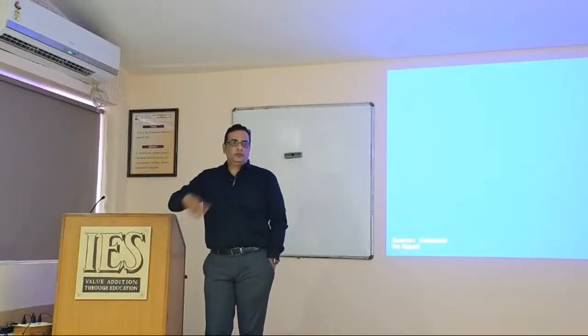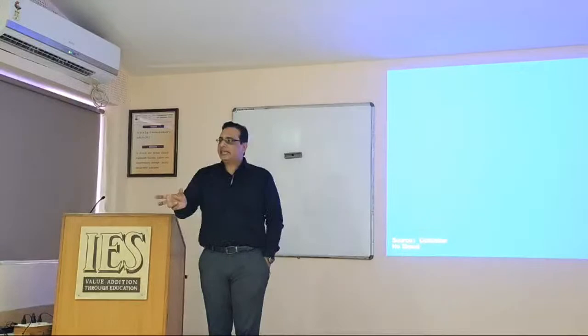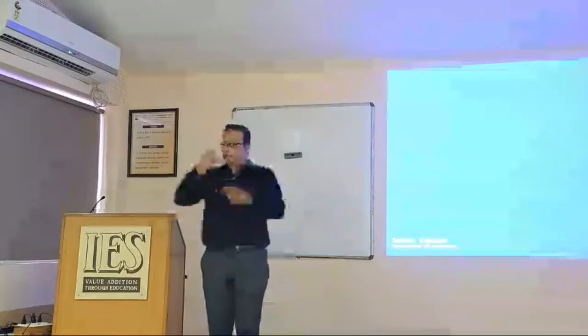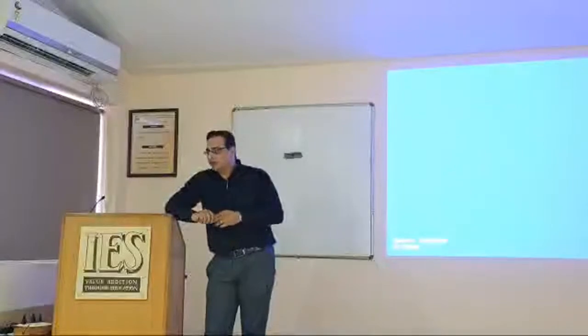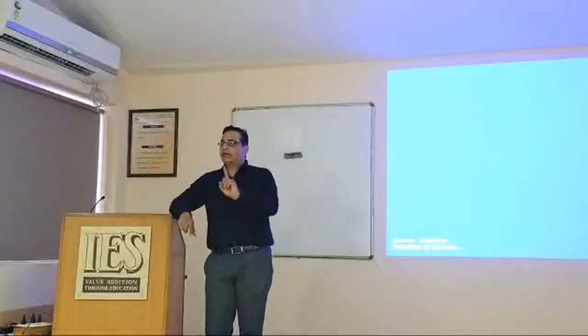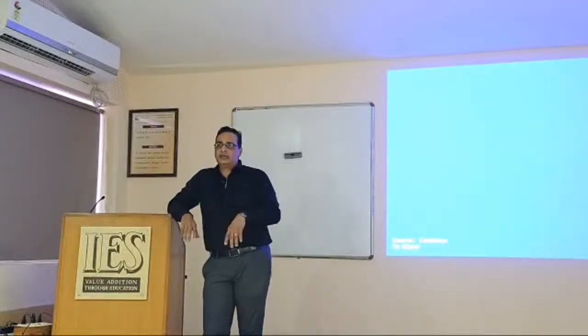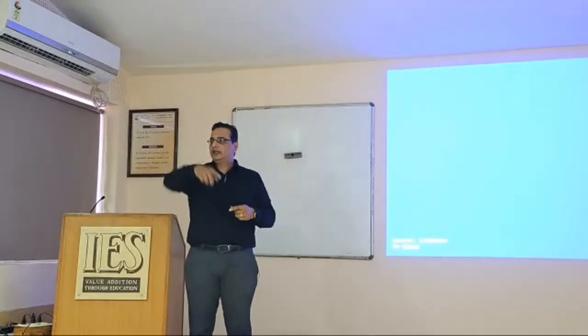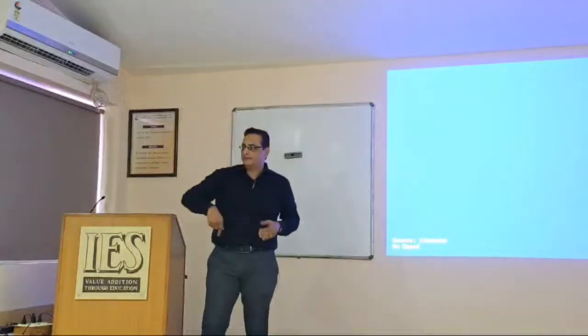So generally firefighting, if you put pipes within the space, we need 900 by 1.2 meters as a standard riser size, in which you put a hose reel and you have the risers, pipe and all. But that's the minimum size. And for every 1000 square meter of area, you need one riser. That is also very important to understand. For every 1000 square meter of usage, you need one riser. So if you have, say, 4000 square meter, you need 4 risers minimum. And the placement of the risers should be such that they are able to take a 45-meter length to the last capturing the property. So that's also a criterion when you look into placement of fire risers.